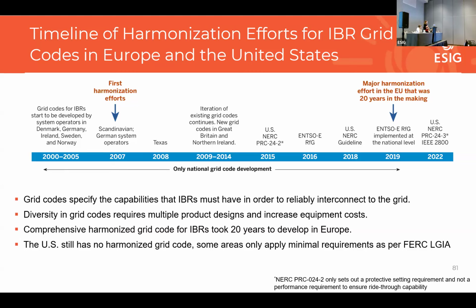First requirements for interconnection of inverter-based resources appeared in Texas. And then some iterations happened in the next 5 years between all of those places that had interconnection requirements developed. In 2015, that's when the first NERC PRC standard was developed, and it had ride-through requirements. But this first PRC standard was a protective settings requirement rather than an interconnection and performance standard for IBR. Then in 2016, that's when the Association of System Operators in Europe came together, and they decided they need to harmonize all of the interconnection requirements that were produced by different countries and have it harmonized on the European level. So they worked for a while, and then I believe in 2016, that's when they came up with the requirement, and then in 2019, that's when it got implemented on the national level.